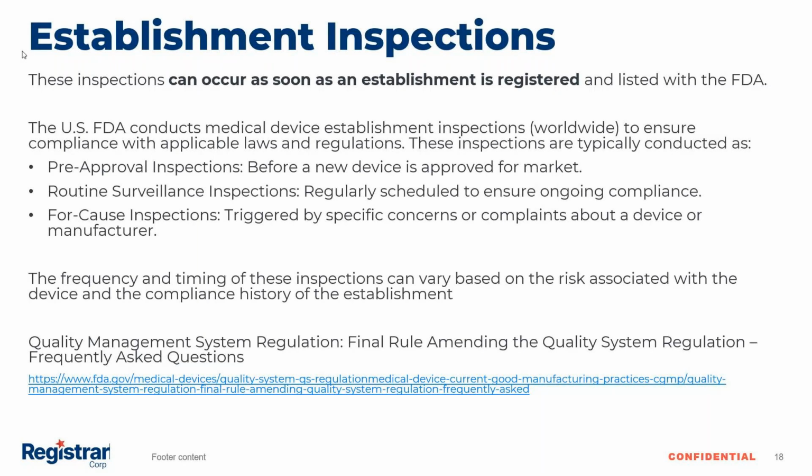To add a little bit to that, if you only deal with class 1 devices, yes, you will see inspections, but if there are no for-cause inspections, meaning there are no complaints about the quality of your devices, inspections do not really occur on a yearly basis. And even for class 3 devices, it's usually not on a yearly basis, around every 2 years.